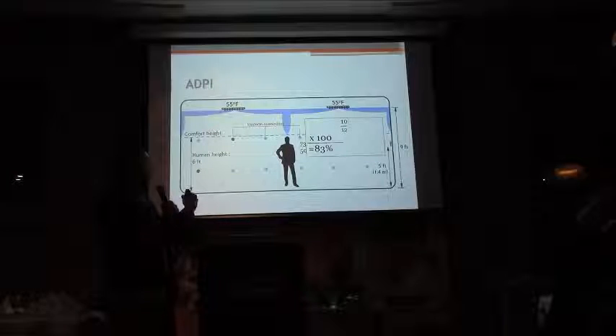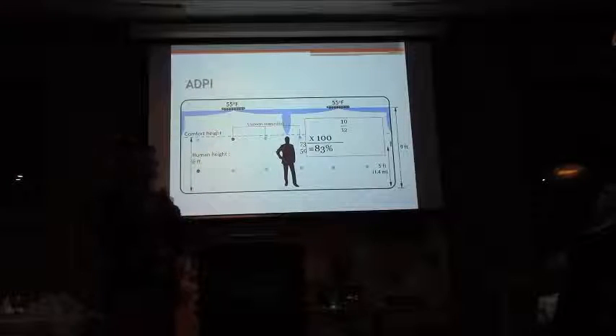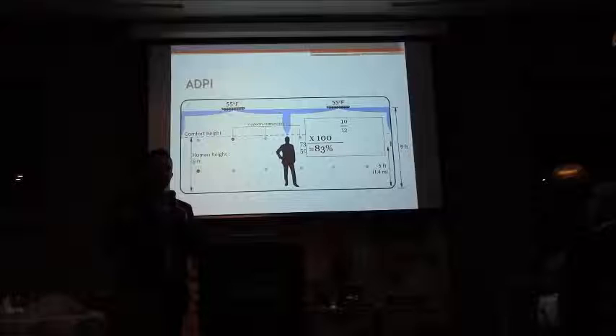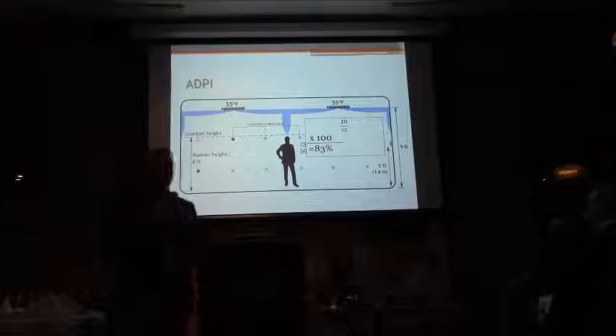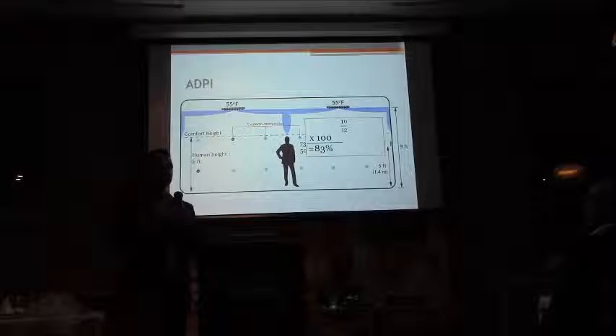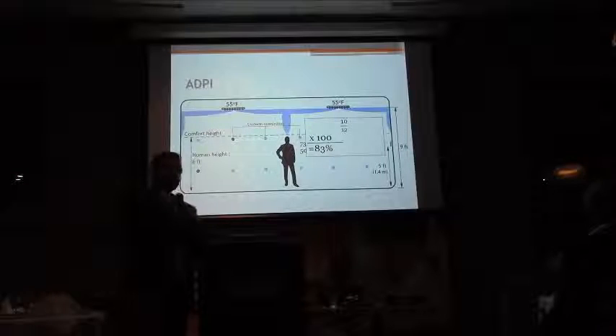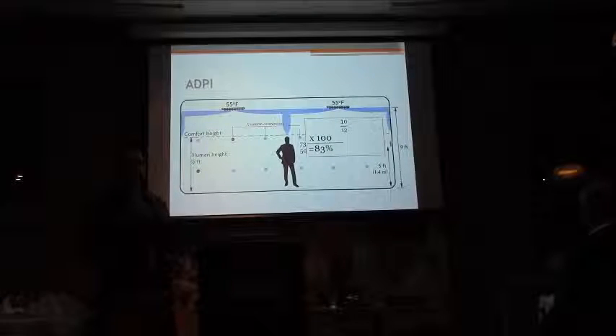So there is one way to go around that. It's actually, ADPI has been linked to something called the T50 on L. It's the characteristic length of your diffuser. So at the design phase, you're able to know based on the heat load, your room dimensions, the throw, the type of diffuser you have, what's going to be your ADPI. But it's a guess measurement when you do it that way.